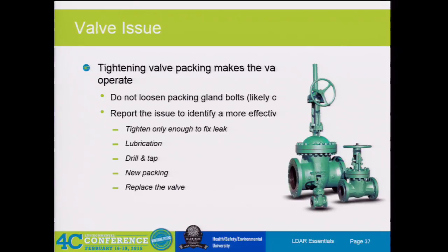Yeah, so tighten it. We were at a facility not long ago. Bronson was with me. Things were leaking fairly often. This was in a tank farm. The repair guy would go out there and tighten those things down, but the operators didn't like it. They would follow right behind these guys after they made those attempts, fixed it, and remonitored it, and they'd loosen them right back up so they could operate that valve. Those things were leaking just constantly. They would leak every time because operations did not want it that way.